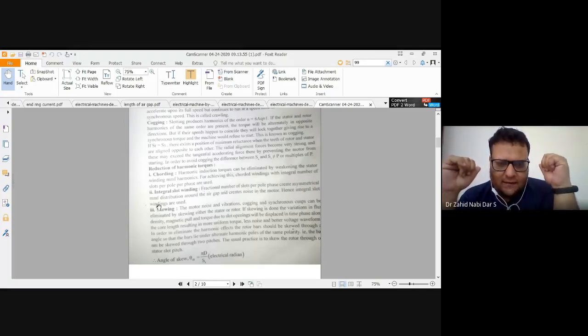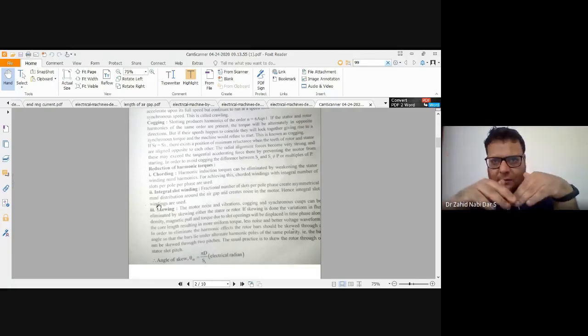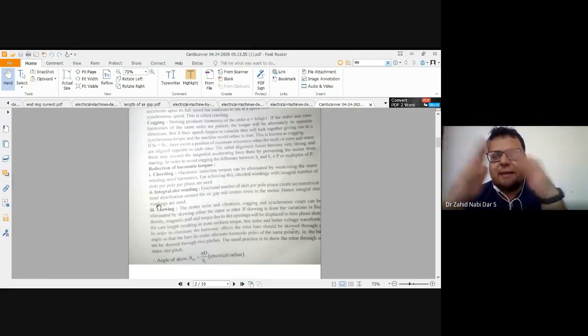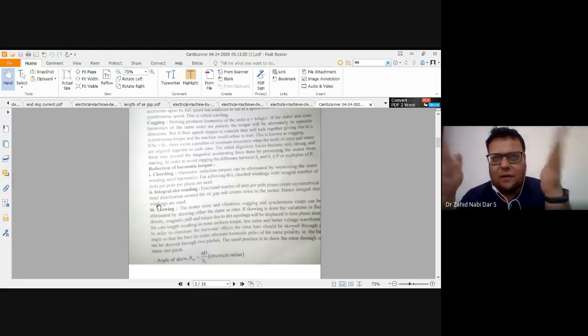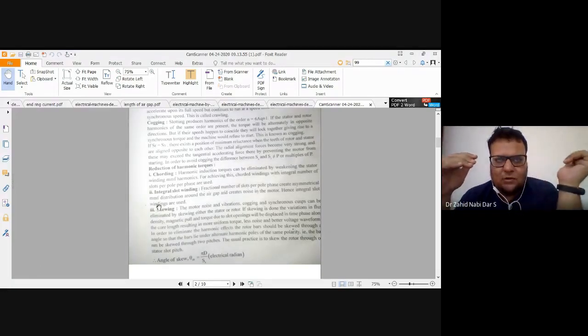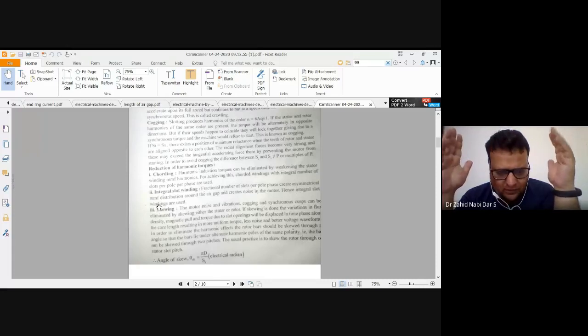Another thing is, by this we are reducing the pole area, just like in your transformers, to reduce eddy current we are reducing the area. Once your area gets reduced, a lesser amount of current will flow, because your current depends upon the area dimensions also. Similarly, here we are reducing the pole pitch. So the harmonics now produced will be in a lesser area, so you will get a lesser component of harmonics.